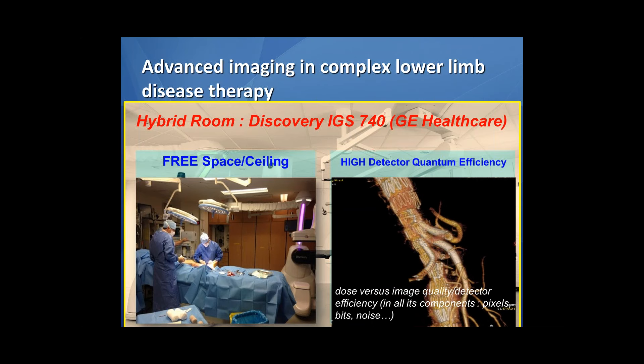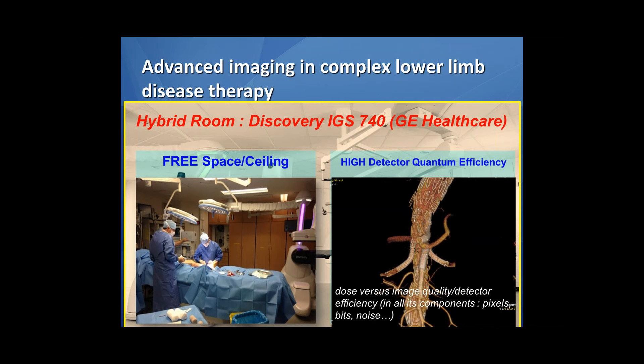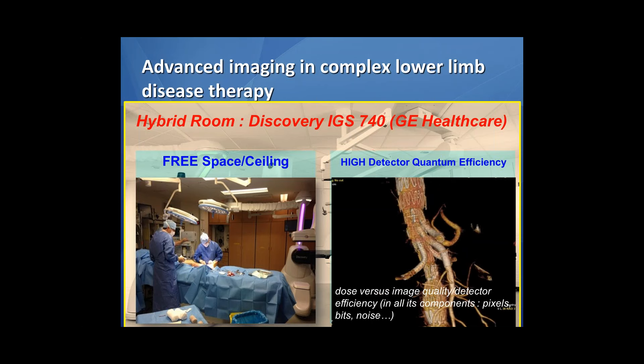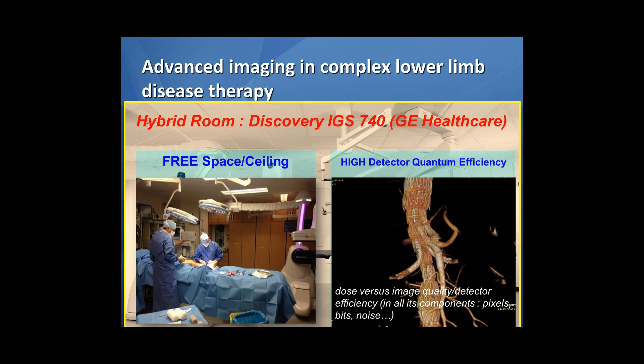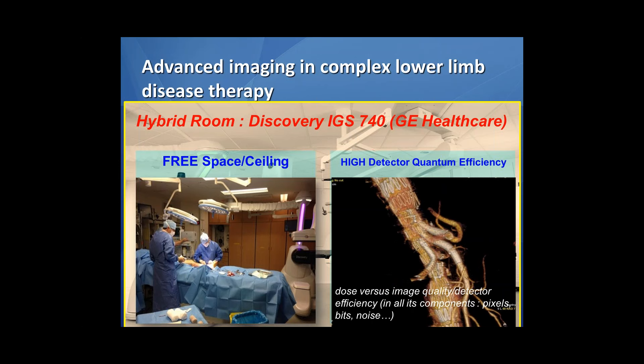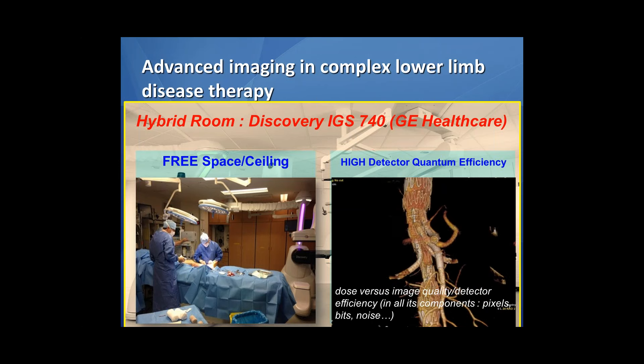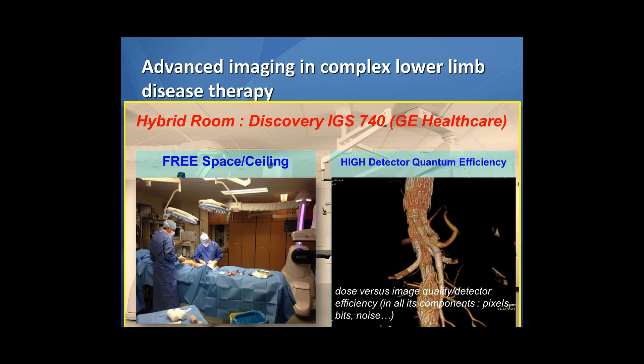On the other hand, we want to have a perfect imaging quality. The best parameter to refer to this image quality is the dose versus image quality over detector efficiency in all its components — pixels, bits, noise, and more difficult parameters for a vascular surgeon. We call it detector quantum efficiency, and I can say that in the Discovery IGS it's one of the highest detector quantum efficiencies on the market nowadays.